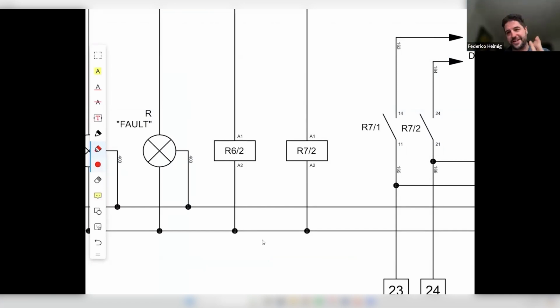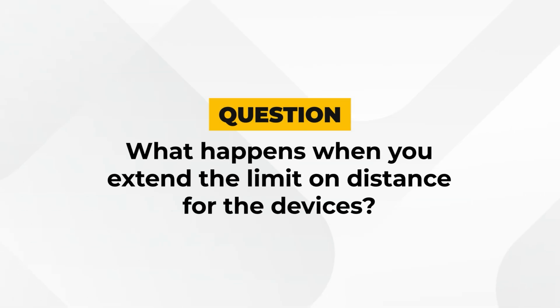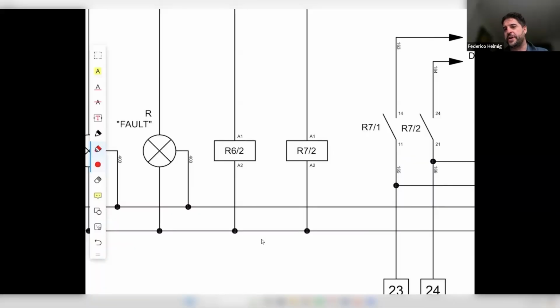Another extra little question is, what happens when you change devices and extend the limit distance? You know that the specifications for many pumps or probes say you cannot extend them more than 30 meters or 20 meters in some cases. Yeah, you're talking about the cable run - you've got to be careful and wary of very long cable runs, just because signals over a long stretch of cable diminish. Think about things like voltage drop and whatnot.